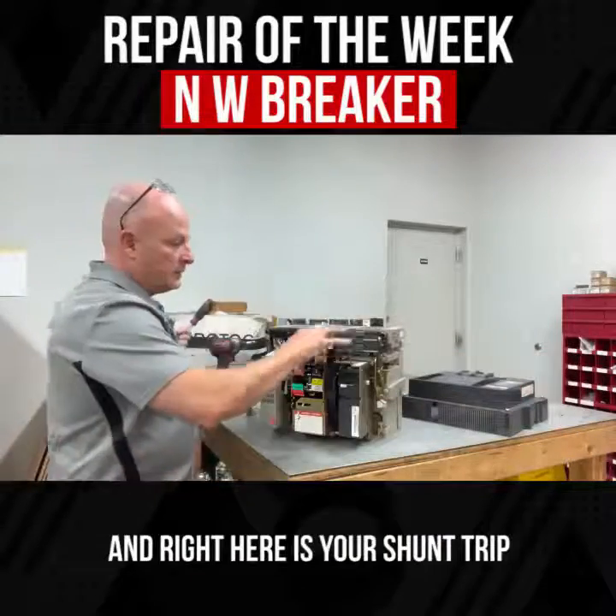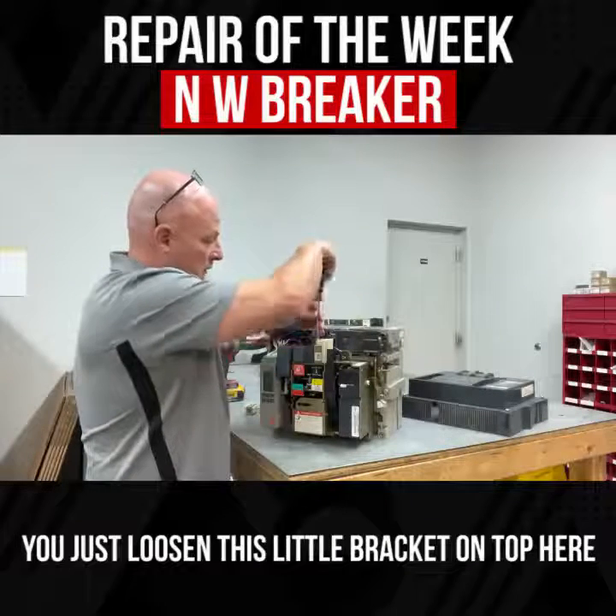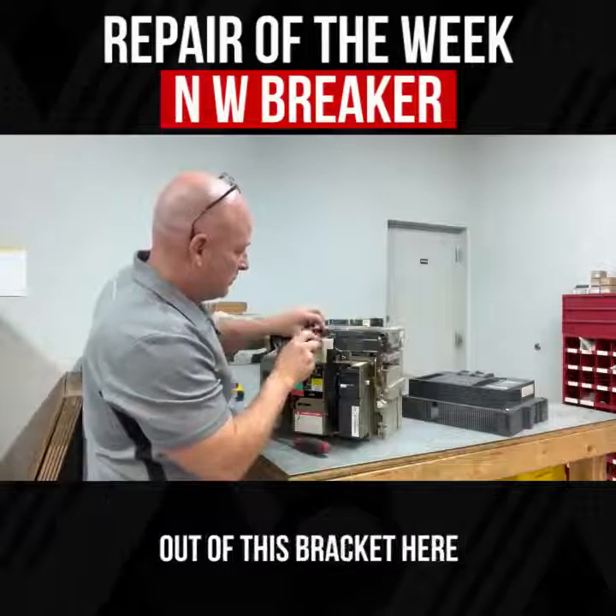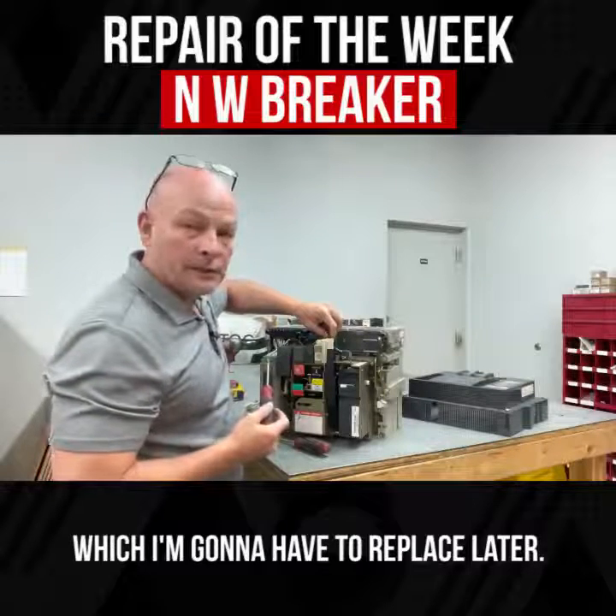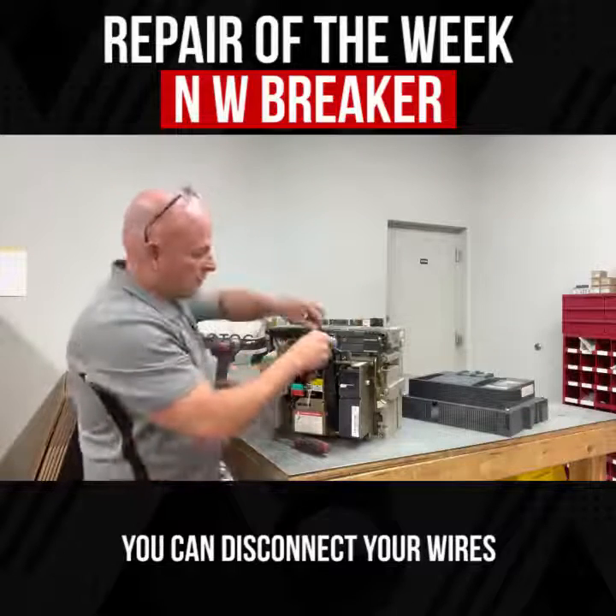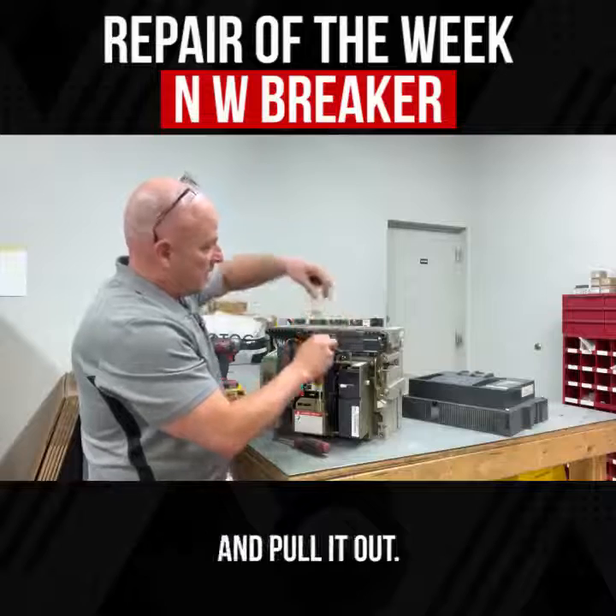Right here is your shunt trip and your close coil. You just loosen this little bracket on top here that holds them down. Then you take these little screws out of this bracket here — which is broken, which I found, and which I'm going to have to replace later. From here you can disconnect your wires for your shunt trip and pull it out.